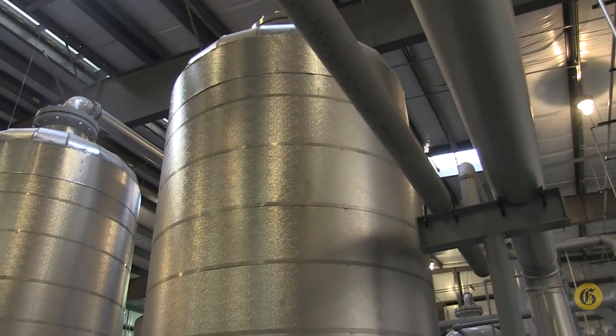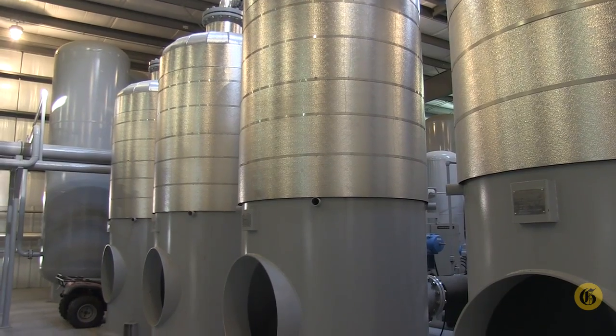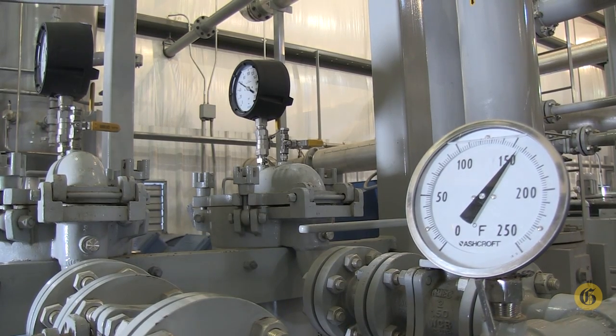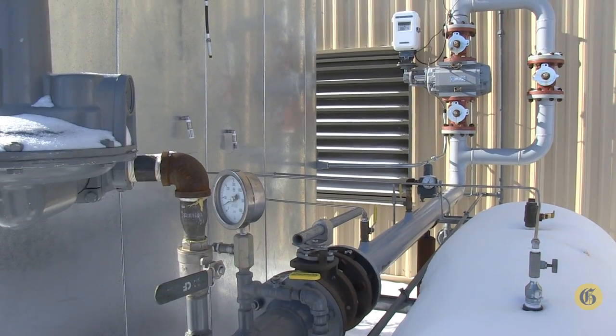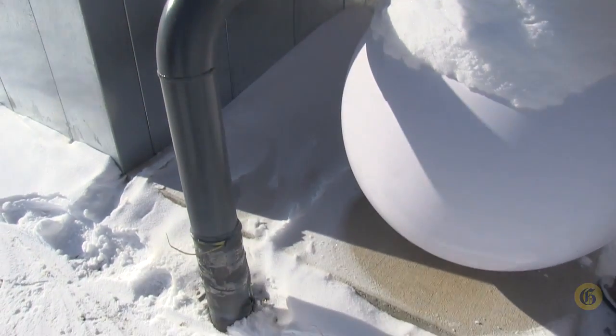In that process we remove the CO2 from the methane. The balance is methane and nitrogen, which goes into our N2 PSA equipment where we remove the nitrogen to get our gas up to spec so we can put it into distribution for consumption in town.